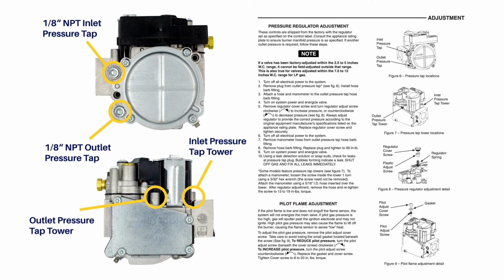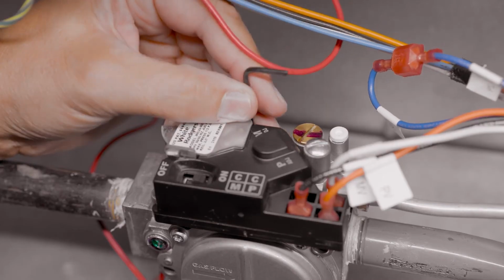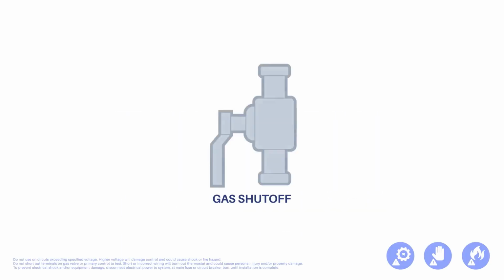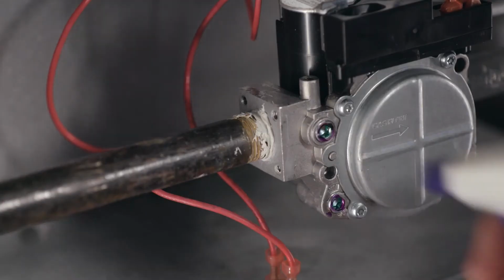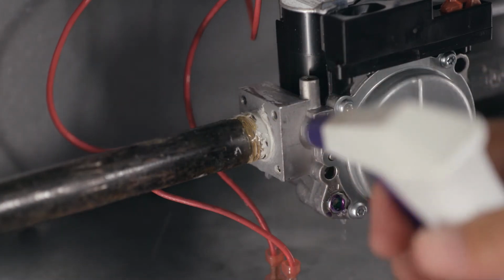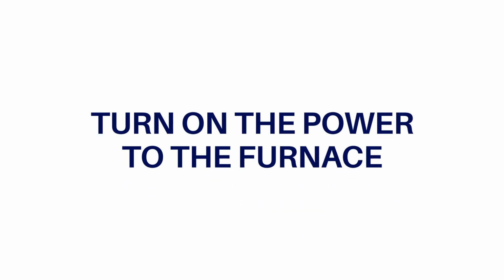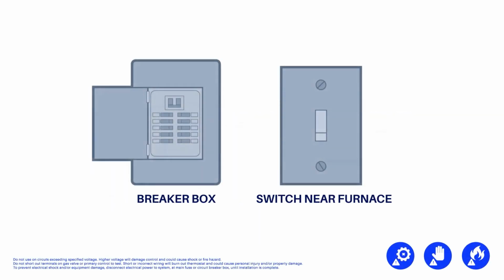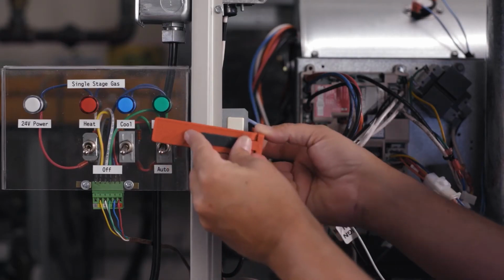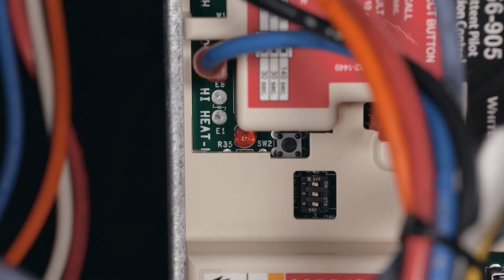Following the instructions supplied with the gas valve, prepare the gas valve for gas pressure testing. Turn on the gas to the unit. Check the gas piping for leaks. Now power the system on by reconnecting the electric power to the unit. Make sure the door switch is engaged. Once powered up, the control will indicate it is ready for normal operation by the red LED turning on. The system is now ready to be tested.